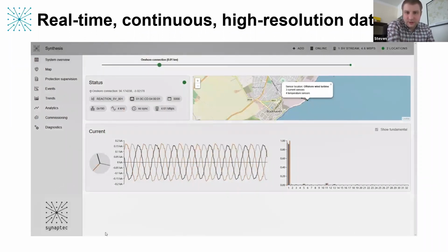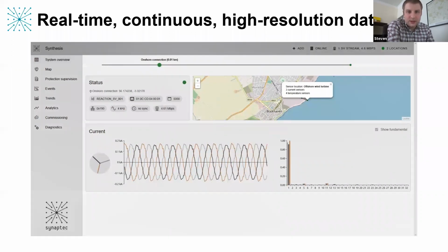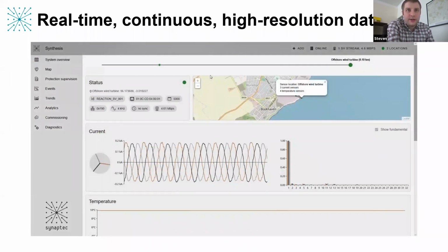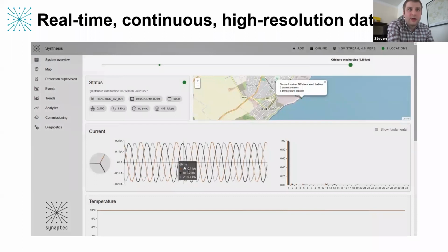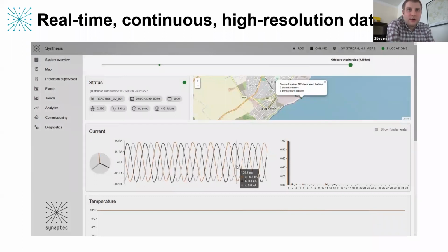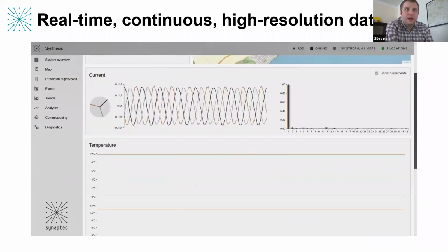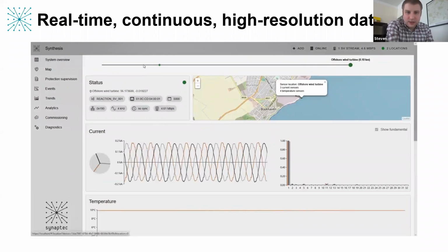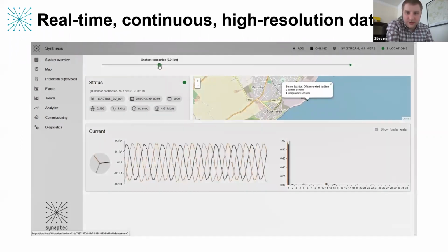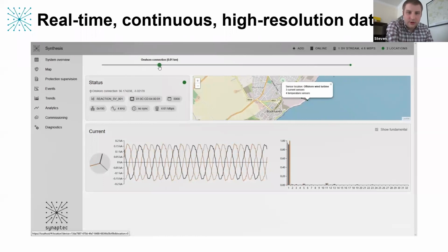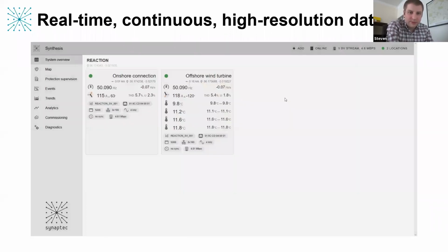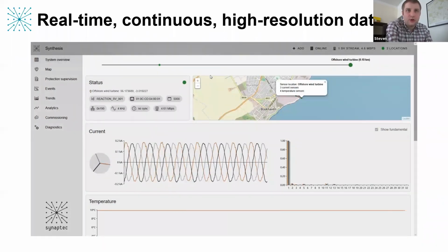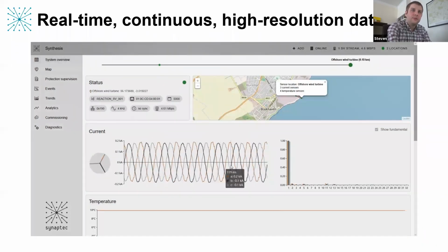You can see on the right there's a harmonic spectrum being calculated in real time for every voltage and current measurement that's built into the system. So it's a bit like having a built-in network of power quality meters and digital fault recorders all integrated into the same system, but without dedicated units needing to be installed. This is all integrated into the platform.